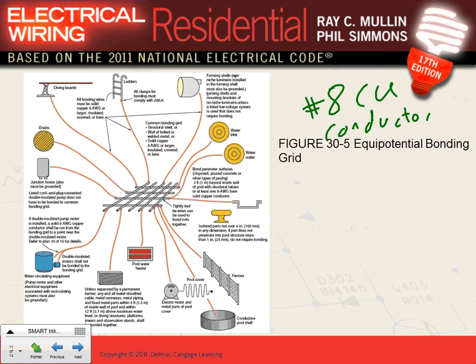The fence, look at the fence. If you have anything, heaters, all this equipment has to be bonded with number 8. Can anybody tell why they're bonded with number 8? If I'm in a swimming pool and this is bonded to number 8, and this thing got hot because the hot conductor touched the frame, and this frame is bonded, what's going to happen to the circuit breaker? It's going to trip. Safety.